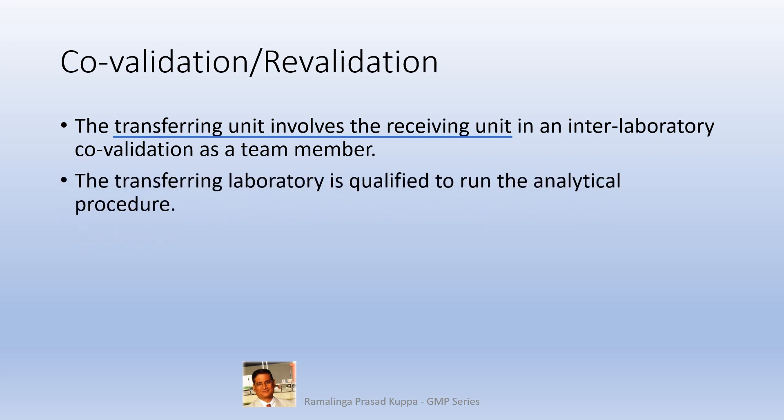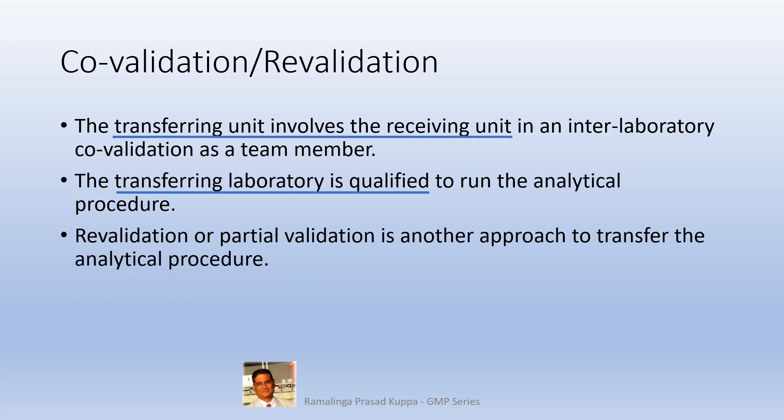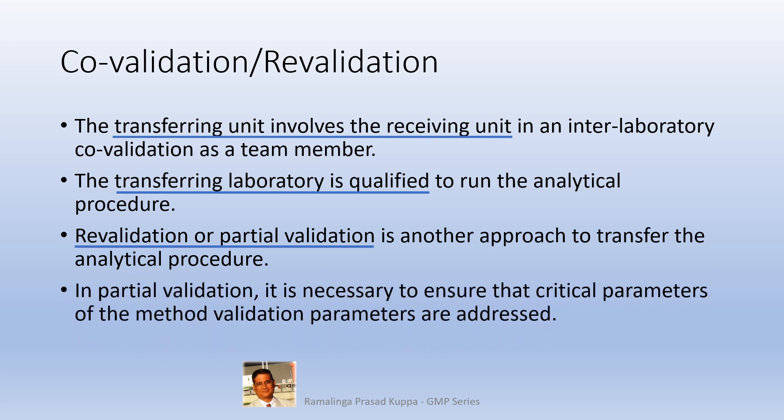The originating unit is authorized to run the test because it developed the test method. Revalidation or partial validation is another approach to transfer the analytical procedure — validating the method once again at the receiving end is also an acceptable approach. Partial validation may also be done depending upon the ease of executing the test method and criticality. In partial validation, it is necessary to ensure that the critical parameters of method validation are addressed, particularly those that may affect the transfer.